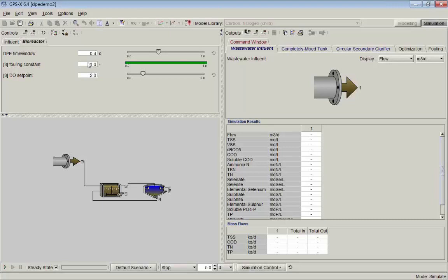So in this particular case, when you have a 1.0 fouling constant, that means there's no fouling at all, it's perfectly clean. As you get a more fouled situation, as time goes on, a fouling constant would become a lower number. You would move down to 0.6 and 0.2 and so on. I guess you never get down that low, but from 1.0, it's faded down to 0.7 or something like that. So a lower value of the fouling constant would indicate a more fouled situation. You're probably pushing a bit more air through there just to be able to get the same amount of oxygen transfer.